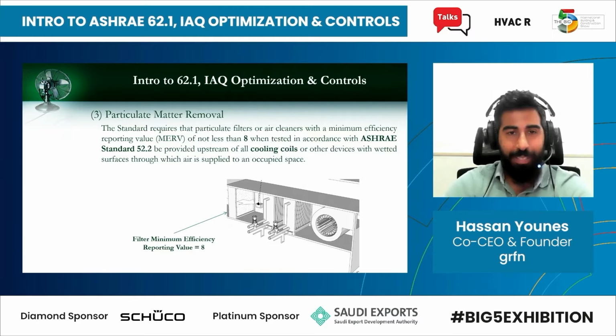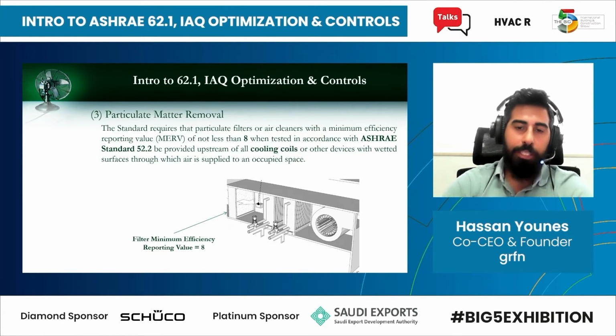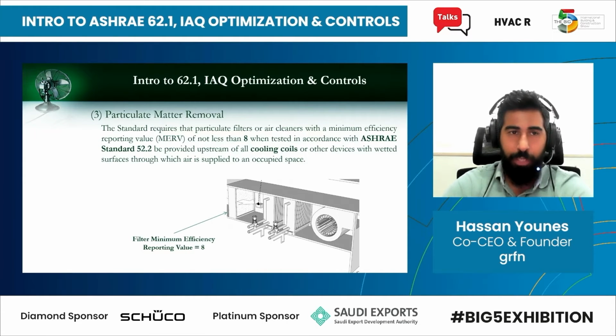Another important point is the particulate matter removal. The standard does require that you have a filter or air cleaner that should have a MERV of 8 when tested as per ASHRAE Standard 52.2. So if you have a coil that might have condensation, and probably any coil in the UAE will have condensation, then you'd need to have a filter. If that coil will not have any condensation, so if you're in a very dry climate maybe, then you might not need to put this filter. But in general, it is required because most of the coils will get wet.